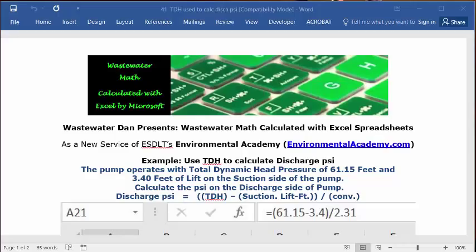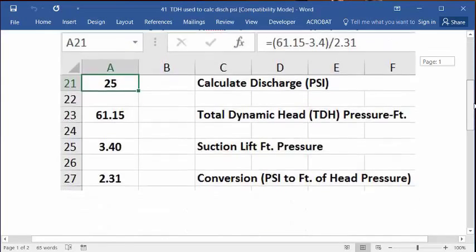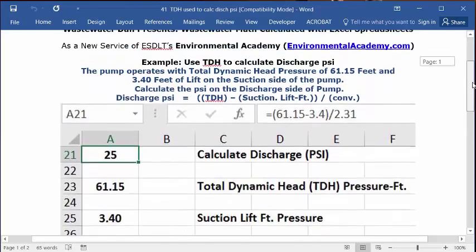So to calculate the discharge PSI, we're going to use the formula that TDH minus the suction lift in feet divided by the conversion factor between PSI and feet of pressure.